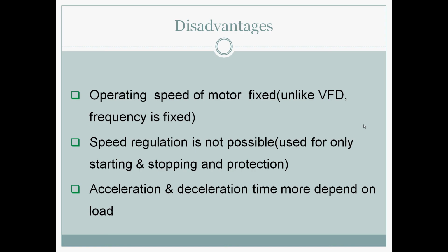Disadvantage. Now comes the flaw. The operating speed of the motor is fixed, so you have to start with a given operating speed and then ramp up. Unlike a VFD, where the frequency is guiding. Here the frequency is fixed, and the operating speed is also fixed. You can't increase it more than you want. Speed regulation is not possible; it is used only for starting, stopping and protection. So speed regulation is not much observed in a soft starter. Acceleration and deceleration time depend more on the load.